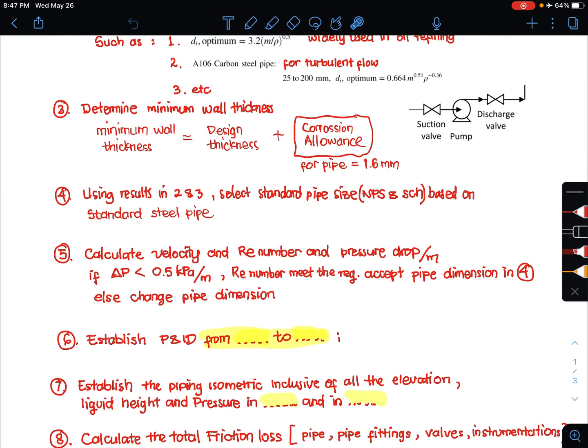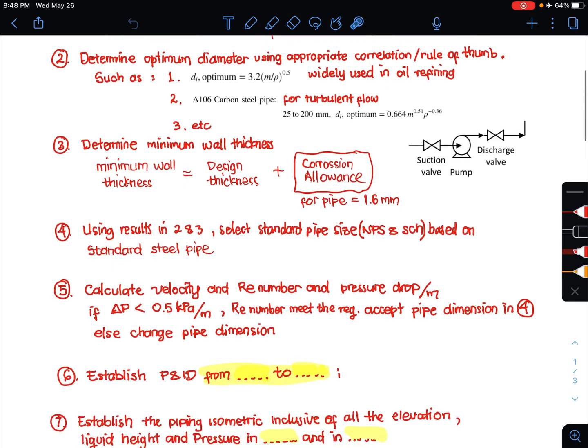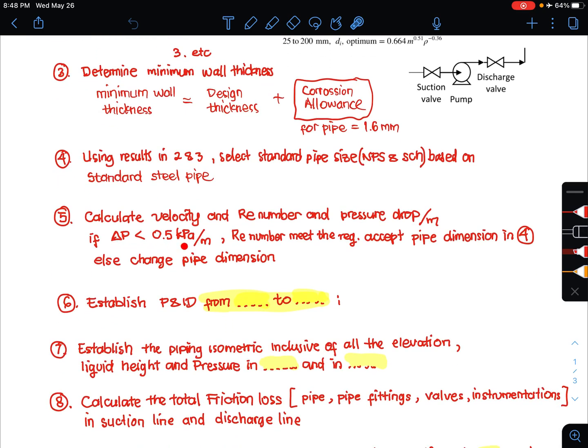Step number 5 is where you calculate velocity, Reynolds number, and the pressure drop in the pipe. If the calculated pressure drop is less than 0.5 kilopascals per meter and the Reynolds number meets the requirement — for example, turbulent flow if that was assumed — then you can accept the pipe dimension from step 4. If not, you must adjust the pipe dimension until both criteria are satisfied.